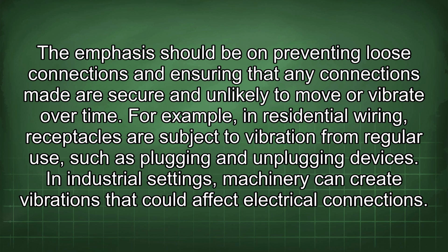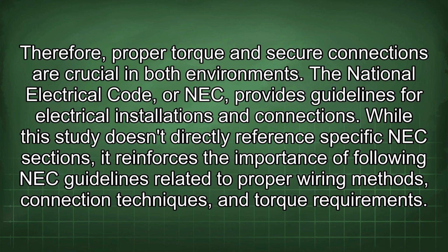or vibrate over time. For example, in residential wiring, receptacles are subject to vibration from regular use, such as plugging and unplugging devices. In industrial settings, machinery can create vibrations that could affect electrical connections. Therefore, proper torque and secure connections are crucial in both environments.